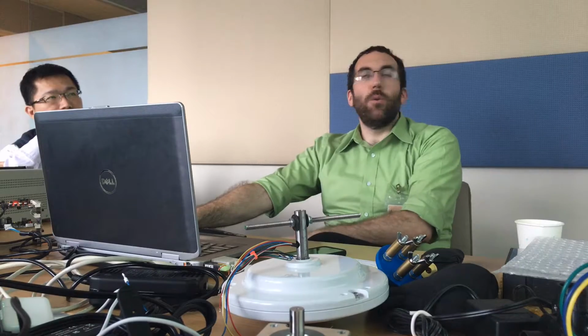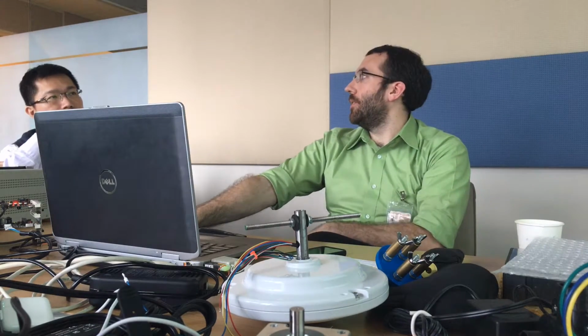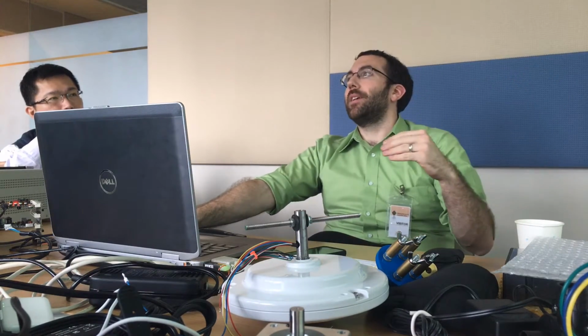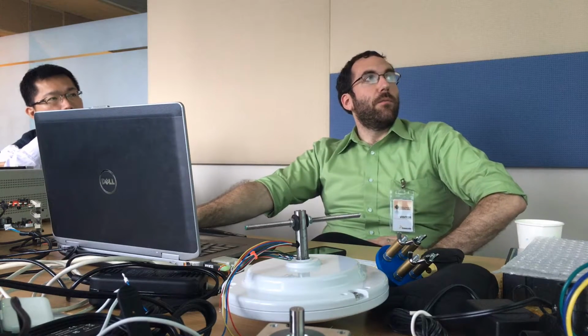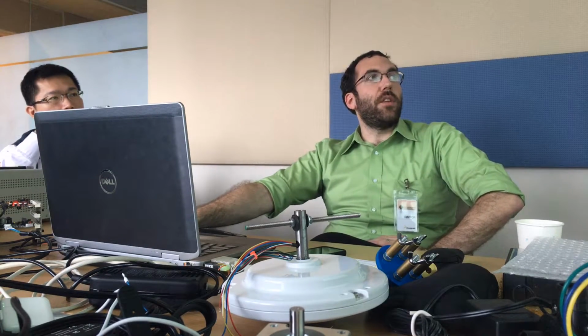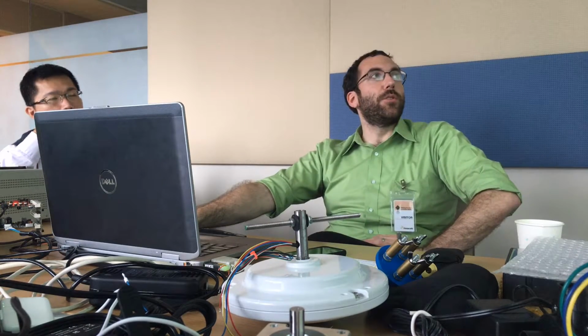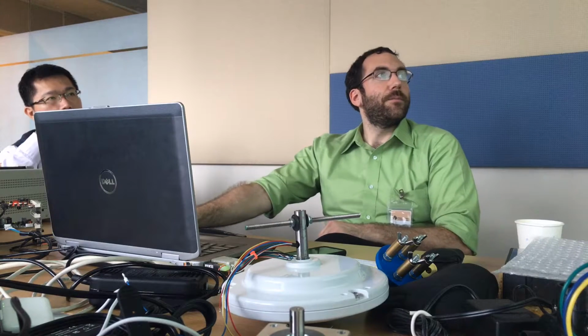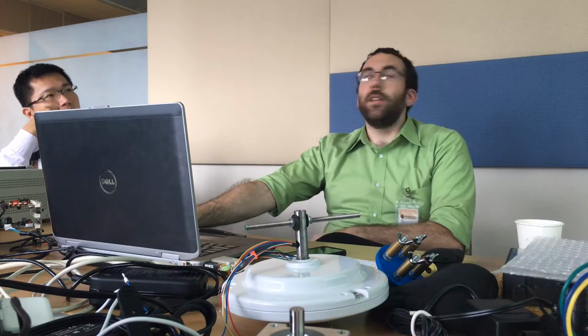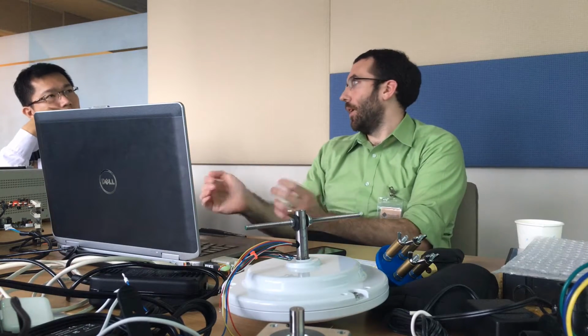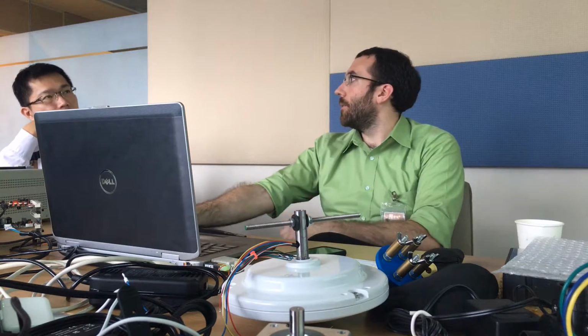So these are all the modes that the user block can go into. And these are all what you would command to get the drive to do something. So you would set, for run speed, the user.state parameter to user run speed, and then it would start running in speed control mode. And if you wanted to stop it, you would set it back to user idle, which just means don't run, don't turn drive off, don't do anything.